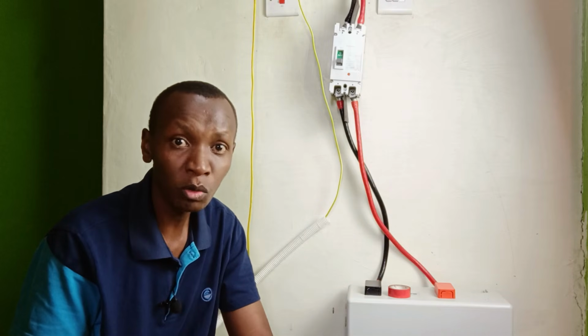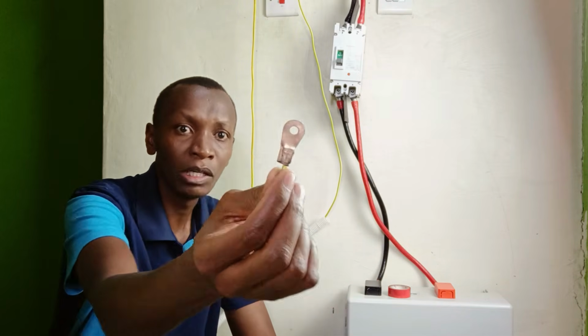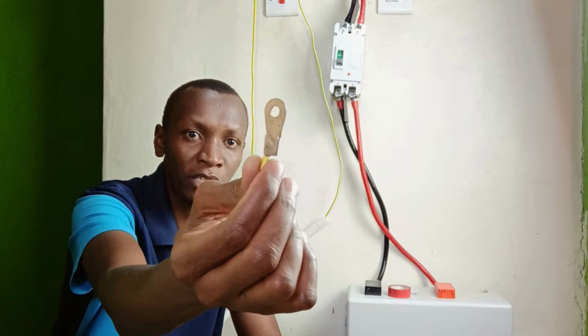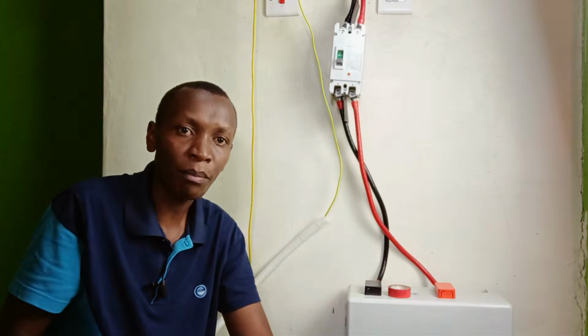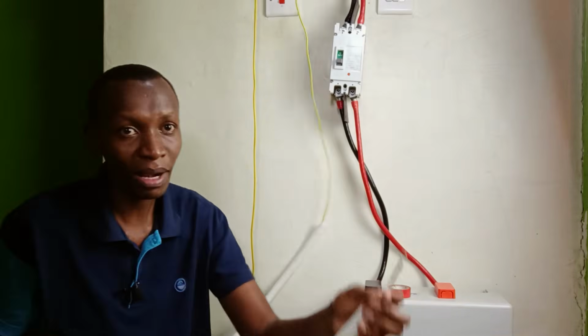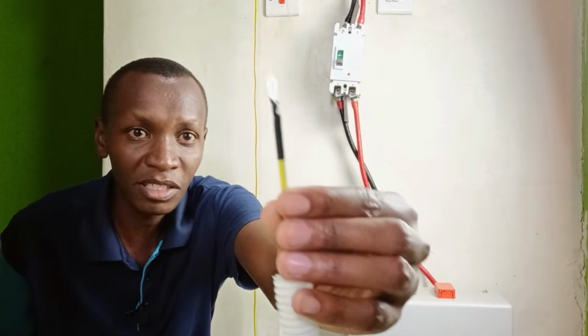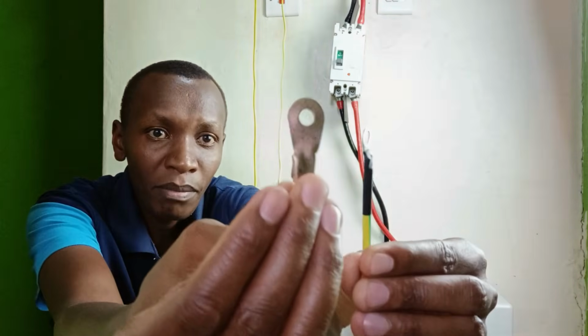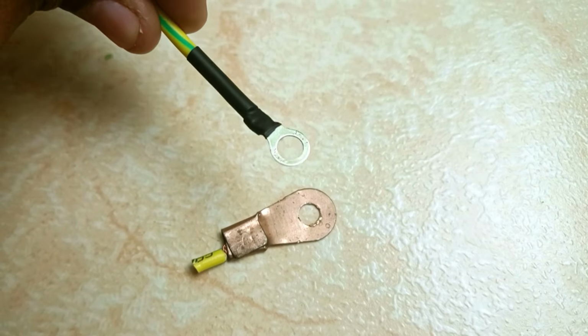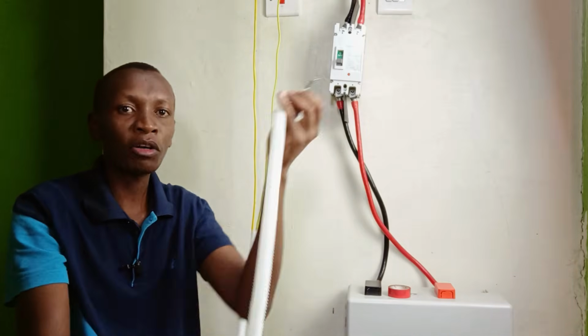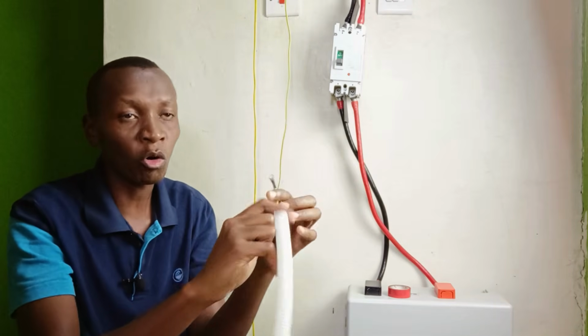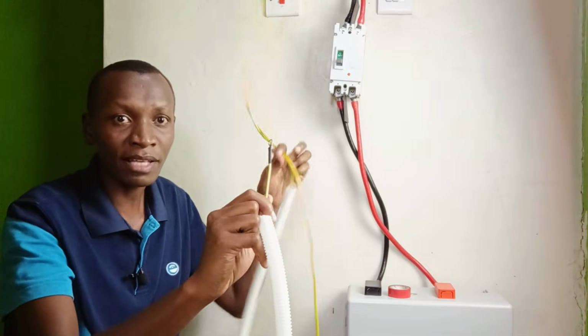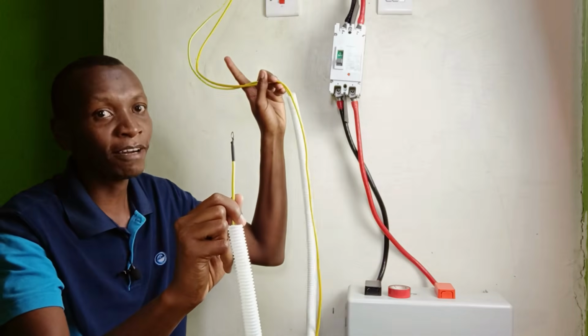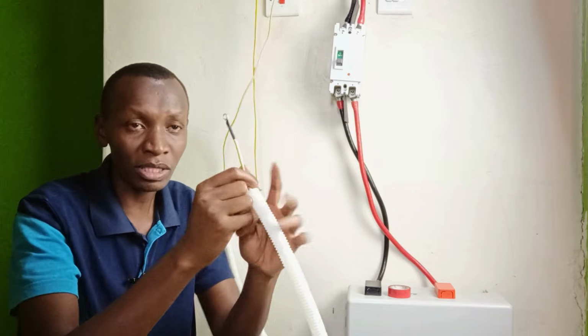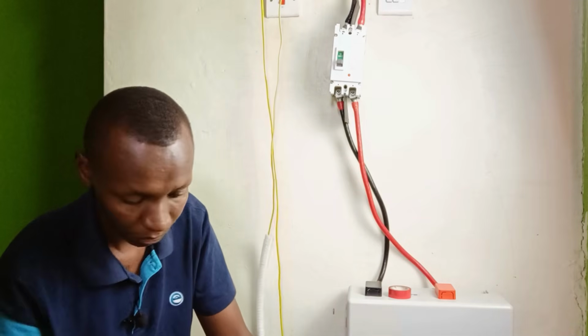If you watched my last 2 live streams, you'll know that I wasn't happy with the crimping job that I did on the protective earth cable. That's why I bought a crimper and some lugs, and this is the end result. This is much better than that. You will also know that I bought this flexible conduit with the intention of hiding the protective earth as well as the Ethernet cable running from the inverter to the battery, and that's what I'm going to do right now.